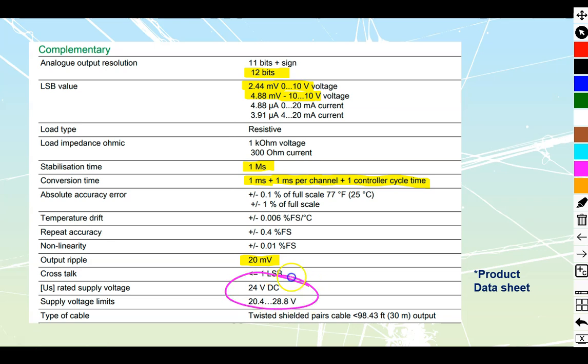This section deals with the power that we need to apply to the card, 24 volts to the card itself. That can go no higher than 28.8, no lower than 20.4. This is the power we're going to take in and run through an actual voltage output to get our signal.